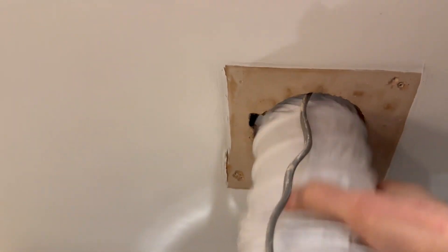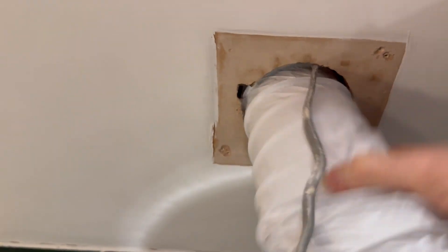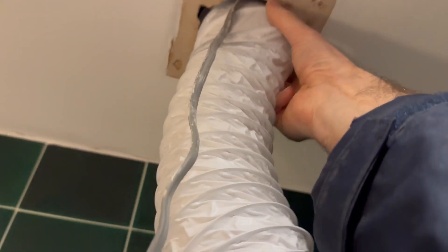Taking out the fan to see what's going wrong — there's way too much tube. It should be 90% taut. The reason why is it creates a lot of resistance if it isn't taut. That's probably as tight as it gets, so if I just remove some, it'll probably solve the problem. I'm going to cut it about there, taking off about a metre, and that should work.